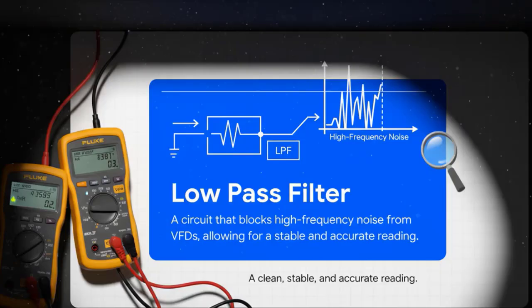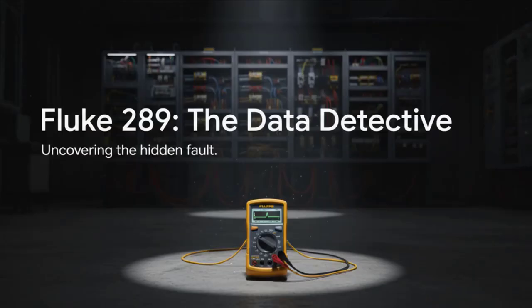And that is where this feature is pure magic. Both the 87V and the 289 have this low-pass filter built right in. It's the special little circuit that just erases all that high-frequency electrical noise coming off the VFD. And what do you get? A clean, stable, and, most importantly, accurate reading. The voltage on your meter finally matches the voltage on the drive. All the guesswork? Gone. Okay, now for the 289 superpower.